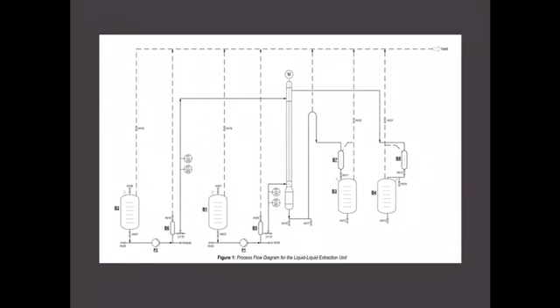The following are general start-up procedures. First, ensure that all valves are initially closed. Next, turn on the main switch at the control panel. Then open the ventilation line valves: HV18, HV19, HV20, HV21, HV11, and HV13.